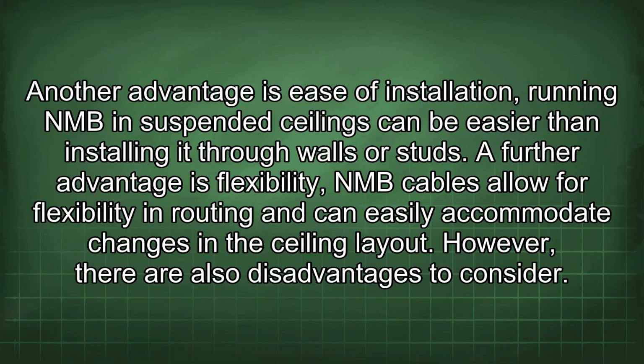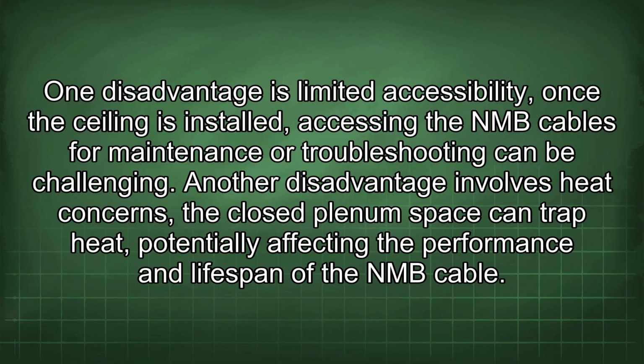However, there are also disadvantages to consider. One disadvantage is limited accessibility. Once the ceiling is installed, accessing the NMB cables for maintenance or troubleshooting can be challenging. Another disadvantage involves heat concerns. The closed plenum space can trap heat, potentially affecting the performance and lifespan of the NMB cable.